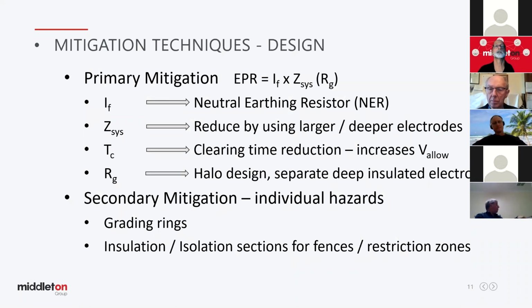Quite typically, resistivities down on your alluvial plains can be quite low and therefore easier to design low resistance grids. But in higher areas, like up in the mountains, I know the Blue Mountains in behind Sydney, a lot of places in Western Australia, etc., there is high resistivity. So burying copper in the ground to try and get a low enough grid resistance to reduce the EPR and touch voltages below the allowable just becomes impossible, or the expense for drilling, digging trenches, installing copper is just not viable.